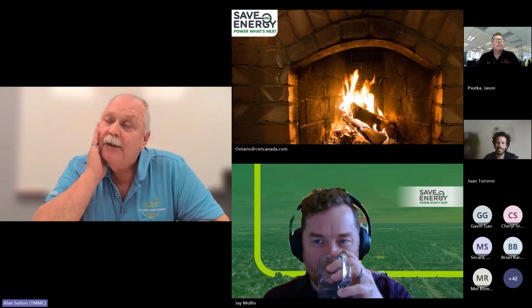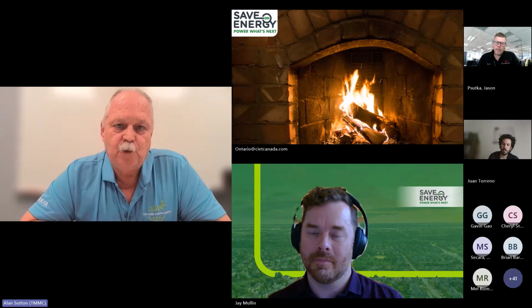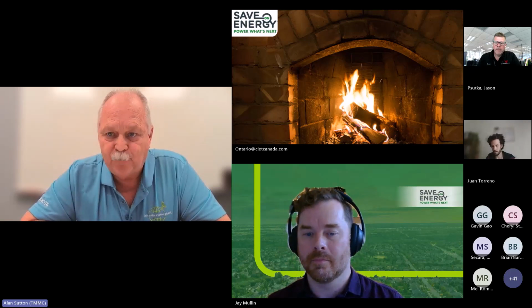That's a lot of questions all in one. Let's start with metering. We do have shop level meters, and meters on our PDPs and MCCs, so we have the ability to track some electrical consumption down to regions of the shop. We do not have the granularity to do electrical measurement on a per-equipment basis. One of our plans is to close those gaps and increase granularity over time, but at the time of this project, we strictly had a main meter going into the plant and 17 sub-meters at various points throughout the line.